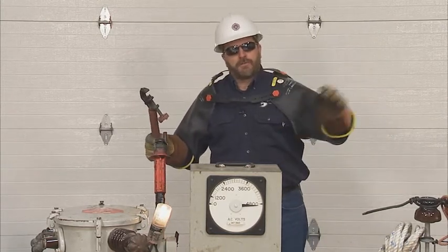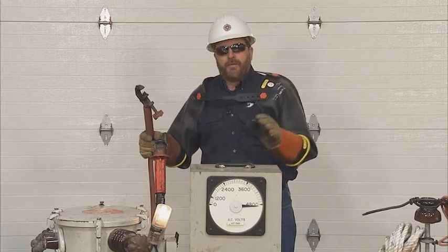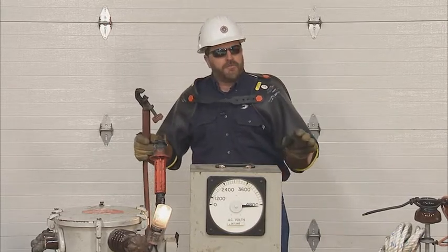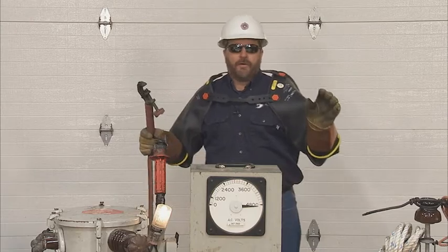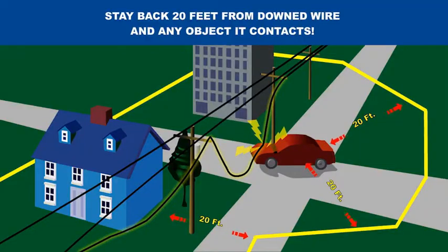Those wires that are down and not doing anything out there are the most dangerous. The ones that are arcing and sparking, we know to stay away from them. The ones that are not arcing and sparking, sometimes you may infringe upon that 20-foot rule. Don't ever get closer than 20 feet from any down wire or anything that wire is touching. If you're putting up down wire tape, be sure you're also maintaining that 20-foot perimeter.